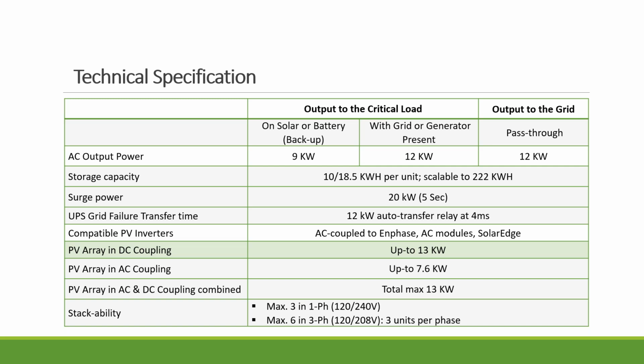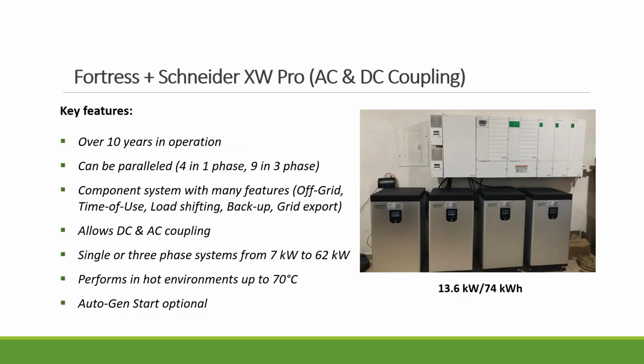Now you can stack 3 of them, up to 36 kW, and next year we'll also be able to support 3-phase. So on each leg you put one inverter to form a 3-phase, eventually up to 72 kW. So that's a solution where you have the inverter, charge controller, and distribution box all in one unit, very similar to a traditional PV string inverter, just with some more: you have the battery terminal, and you can connect to the backup load panel as well as the generator input.